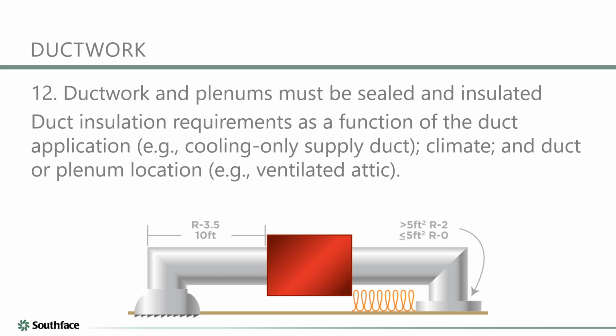Yeah. And as you mentioned, I think we have almost a bigger focus on this in the residential world, where we have hammered into people the importance of duct sealing, and we have trained people on how to do duct sealing, and we have requirements in our code for testing, for not only sealing the ducts, but testing the ducts for tightness. And over here in the commercial world, on one hand, I think we benefit. A lot of duct systems in commercial buildings are inside the building envelope. And in that way, the duct leakage is not as much of an energy penalty. Duct leakage is a big energy penalty when the ducts are located outside the building's thermal envelope. In a house, in a residence, that's very typical, where duct systems are just up in an attic and the insulation is on the ceiling. And so they're up there and they're outside of your thermal envelope. They're outside of your building. And therefore, when they leak, everything they leak is a waste of energy. It's all energy waste outside of your building's envelope.